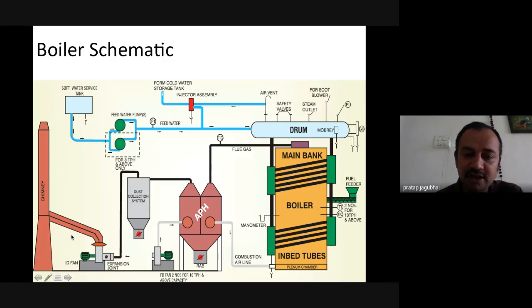The purpose of the fuel cycle is to burn the fuel by mixing it with the air, which is delivered through the FD fan. Fuel is burned inside the furnace, and heat is generated due to the combustion. And due to the convection, the ID fan takes away the flue gas by overcoming the resistance across the emission equipment, air preheater or economizer, and the top of the furnace height, the middle sections. The ID fan functions to carry away the flue gases from the outlet of the combustion and leave through the chimney.